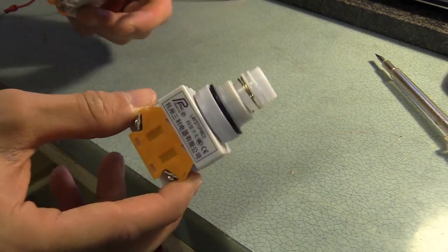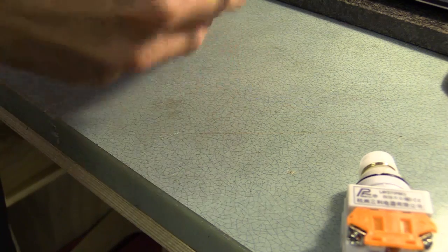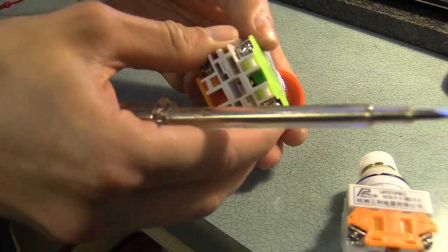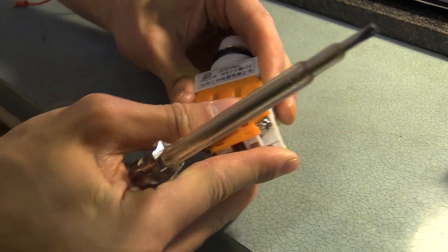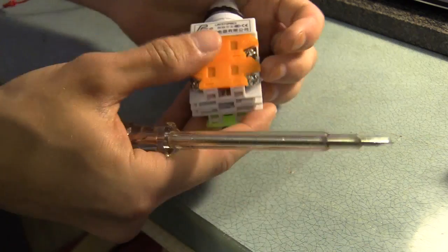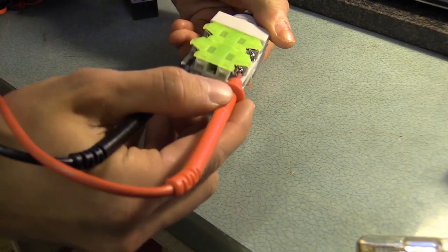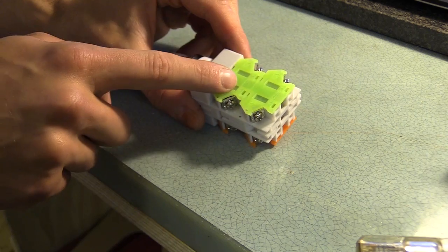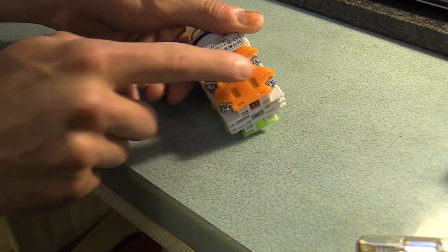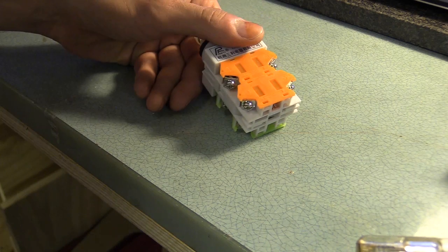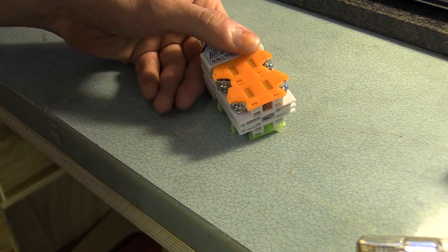I'm going to go back to the e-stop now. I'm just going to undo the back of another one. I'm simply going to clip this on. That's the normally closed side. That's normally open. I'll connect these two terminals to the VFD and these two to the abort terminal on the controller. I might even connect these two to the power supply of the controller just so the power gets killed as well. I think that makes sense.